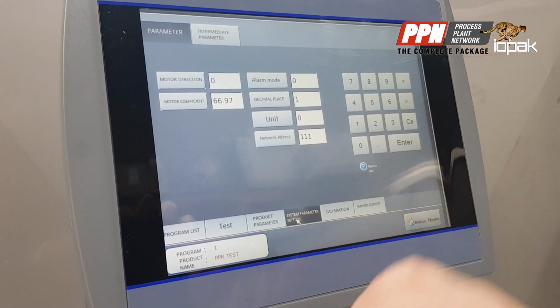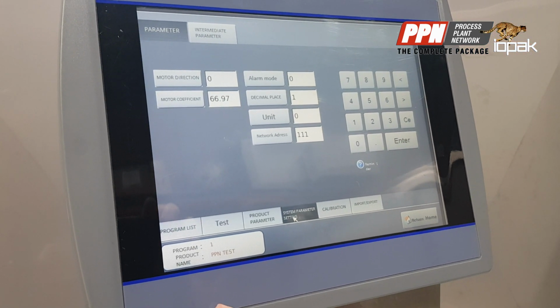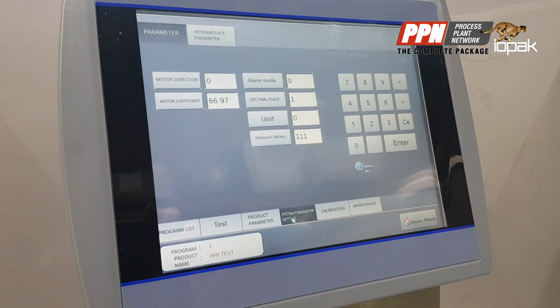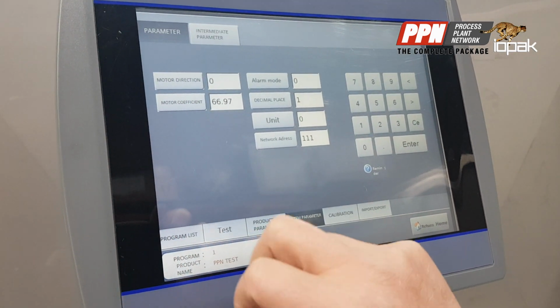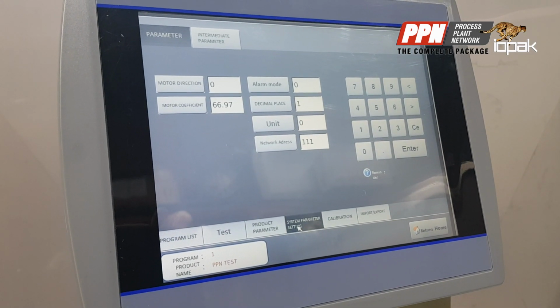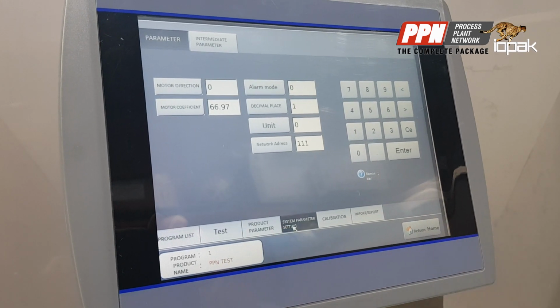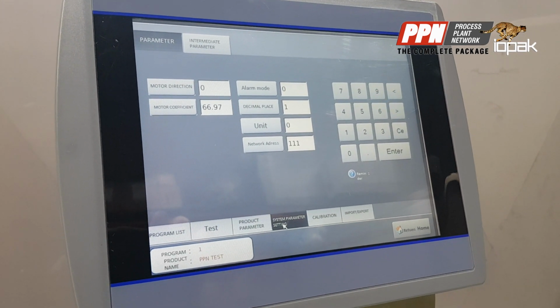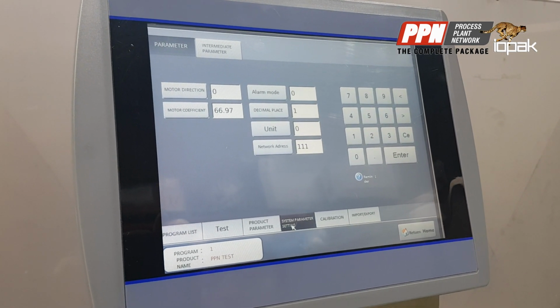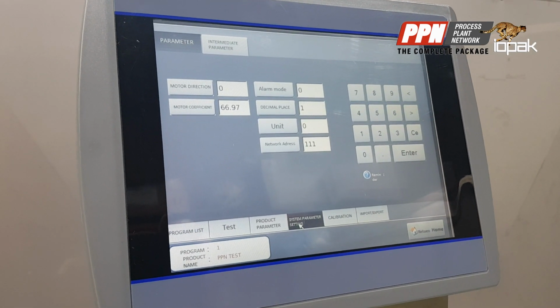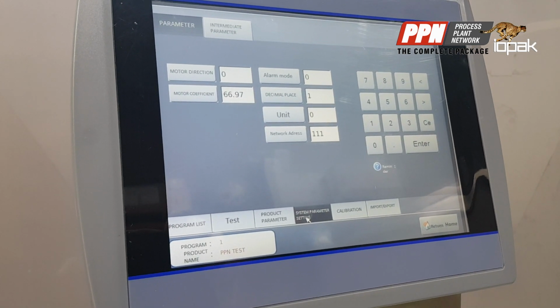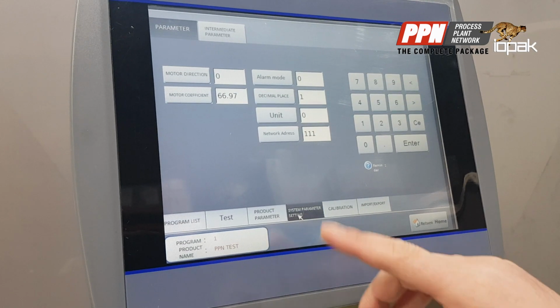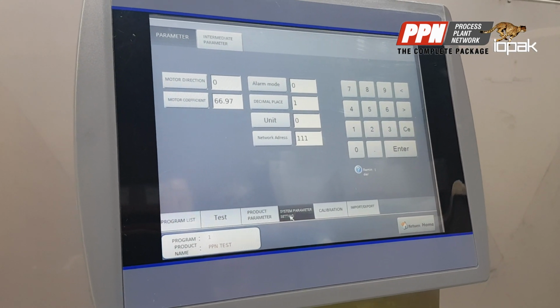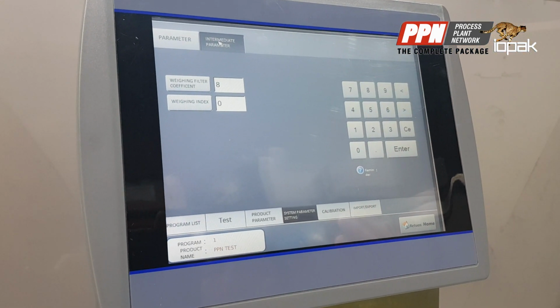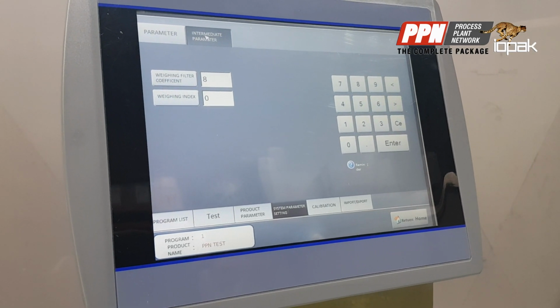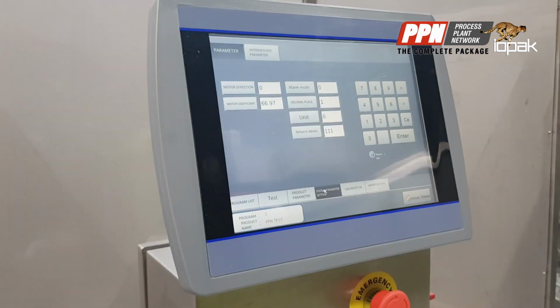The next one I'm going to show you is the system setting. In system setting, we have some features that are preset in the factory, only accessible in level 3 and level 4, like the motor direction and the motor coefficient. If you do need to change or replace the motor, those are the values that we need to change. And the alarm mode, which is whether the machine is going to stop or the machine just rejects and continues. The decimal place display on the screen, the unit, whether it's SI or BSI, British unit, the network address, which is for Ethernet communication with the remote computer, and we also have a weight filter that is preset in the factory for the different load cell that's been used.